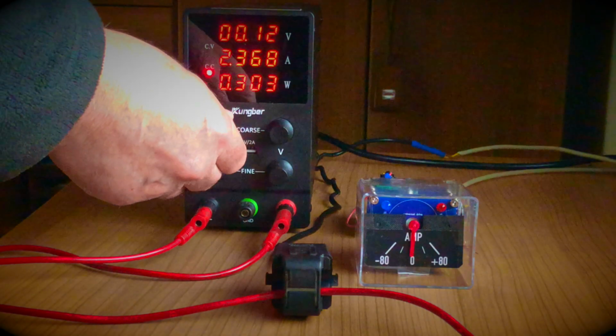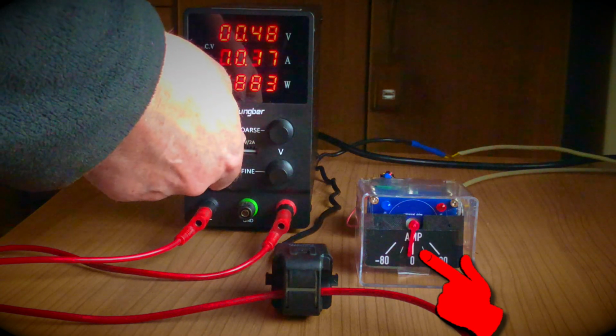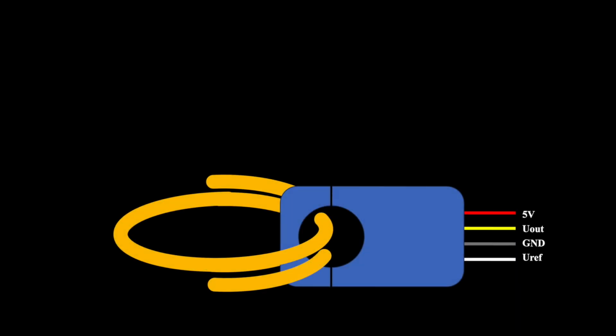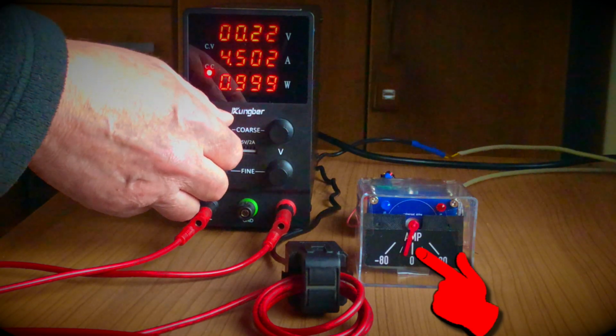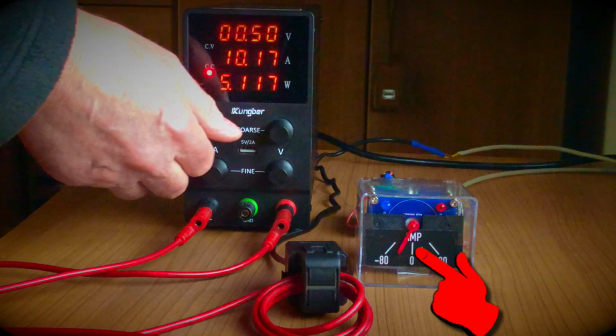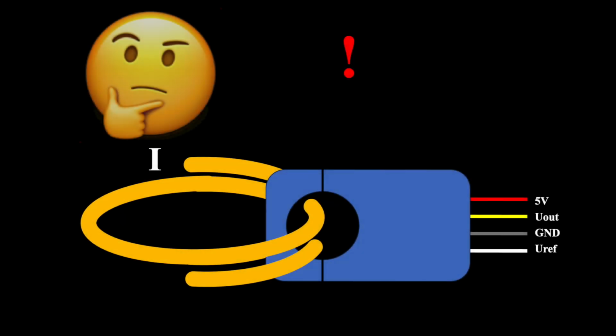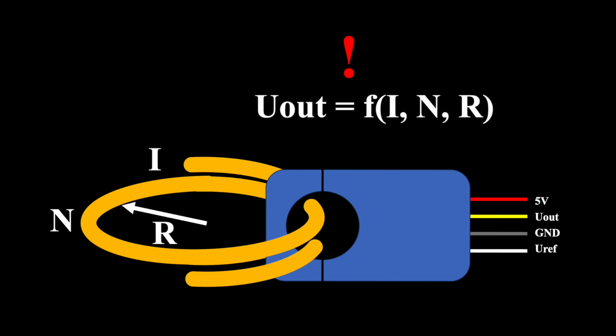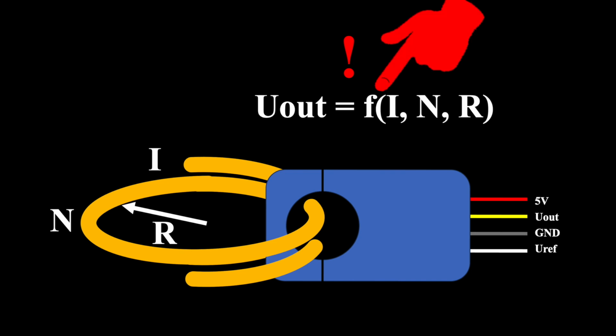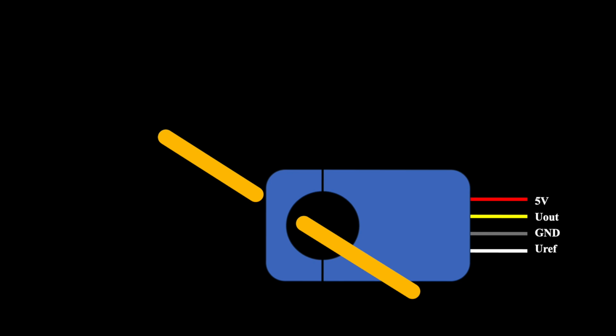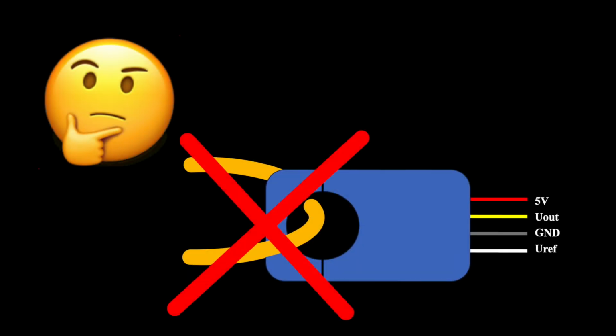Now I'm telling you a trick to increase the measurement sensitivity. Looping several turns through the sensor is increasing the output signal. But be careful. It depends not only on the number of turns, but also on the diameter. A smaller diameter is producing a stronger signal than a large one. So you need to recalibrate, because the sensitivity doesn't just increase by a factor being the number of turns. We will explain the physics behind in another video, but an immediate takeaway from this is the following. The cable should be straight at the measuring point, because loops and bends could cause measurement deviation.